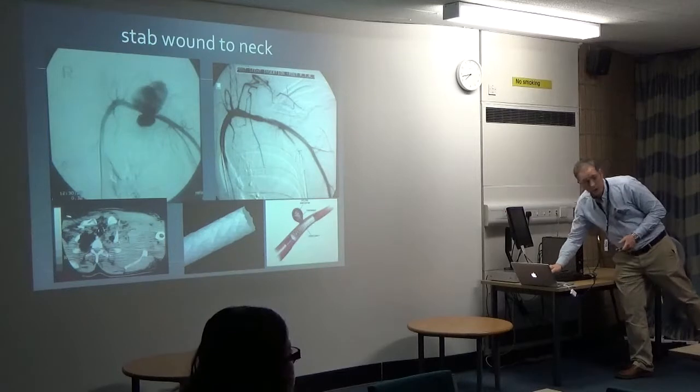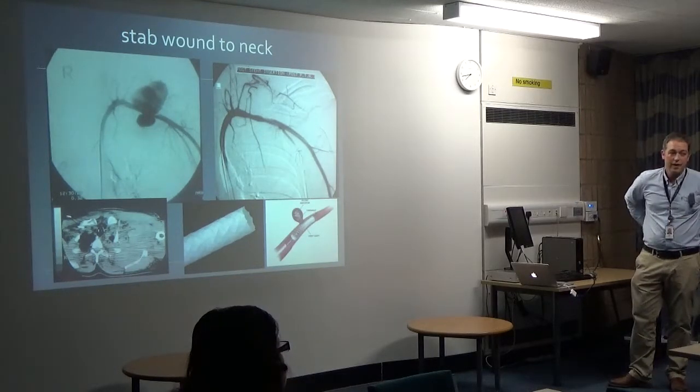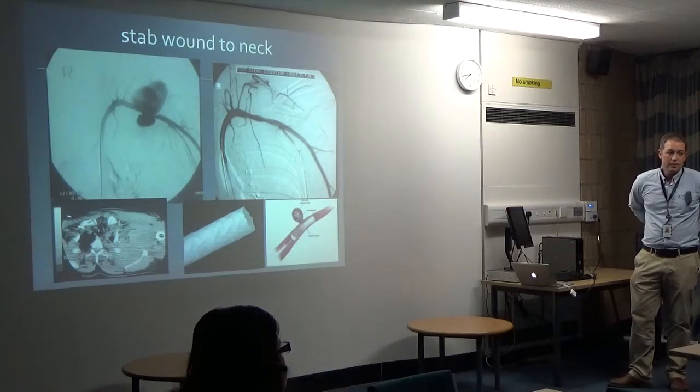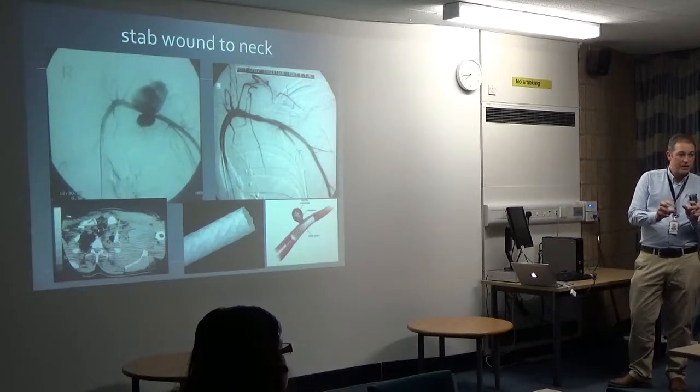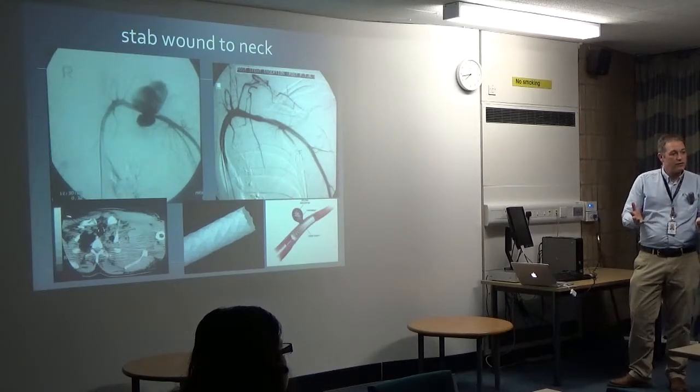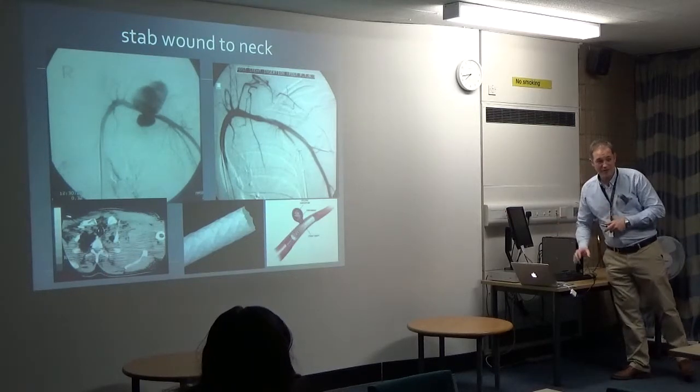Are the stents left in permanently? The stents, yeah. Yeah. They're not renewed after a length of time? No, they're permanent. They're all completely sterile and they've been designed to last for life, essentially. Thank you. Yeah, they're our gift to the patients.